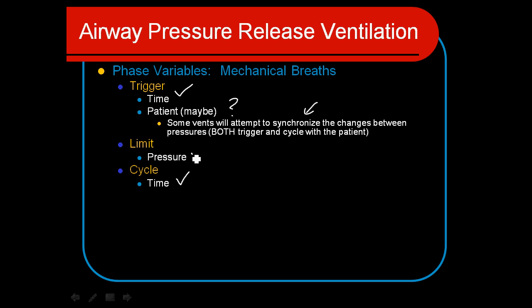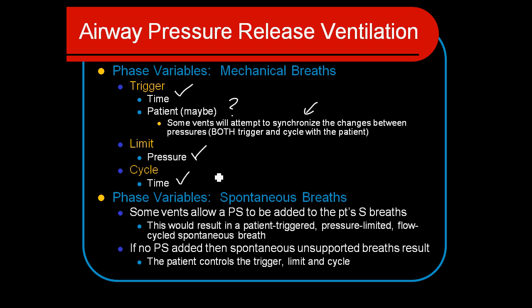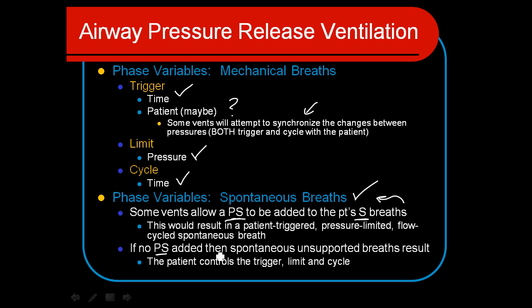For the phase variables, we do allow spontaneous breathing at any time during either the inspiratory or during the short expiratory phase. On some manufacturers, we can even have pressure support to augment the patient's spontaneous breaths during that spontaneous breathing. Often there is no pressure support added, and the patient is simply spontaneously breathing in and around the pressurized cycles of the ventilator.